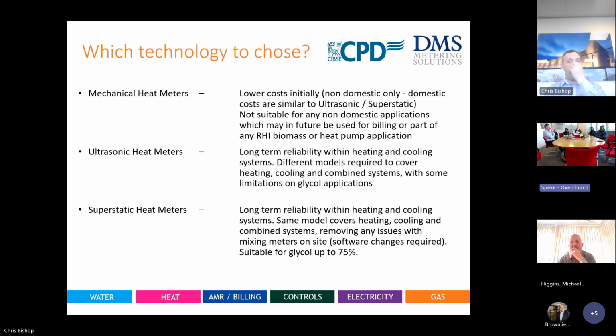Different models are required to cover heating and cooling combined systems. Ultrasonics have a tendency where, instead of having combined heating and cooling meters, when you purchase or design one, you have to design it as a heat meter, a cooling meter, or both. We have a lot of clients that get that wrong when asking for it, and some of our competition gets it wrong in supplying it. With regards to superstatics, long-term reliability within heating and cooling systems, just like the ultrasonic: no moving parts, debris in the system, no problem at all.